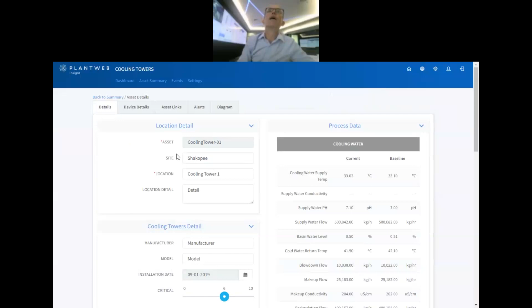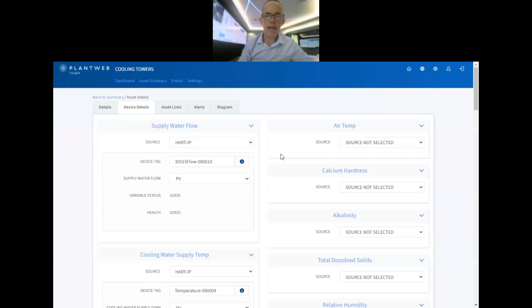Let me look at the device details. So here I can see that in this particular one, this flow measurement is coming in through HART IP, but I could also configure it to OPC UA. Let's say if the data comes in through my existing DCS or historian. But if it's a wireless HART device, the data will come in through HART IP. And if you're familiar with HART, you will also recognize this primary, secondary, tertiary, and quaternary variables. So multiple variables can be accessed from the HART device this way, wireless HART transmitters. I think you get the concept.